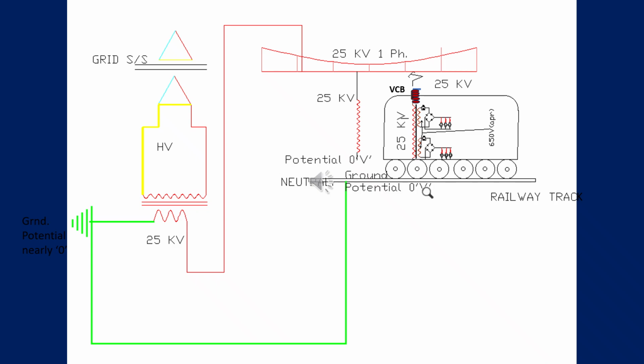So this is what we are receiving in the traction substation, and what a beautiful thing we have done there. One phase, the yellow phase, we have earth connected to ground. So many people are confused: sir, phase to earth, it will be a short circuit. No, it will not be a short circuit. What is a short circuit? A short circuit is to complete an electrical circuit without any load, without any impedance. But here you see the secondary of the 25 kV, one end is connected to the ground. So this yellow phase will attain zero potential, and the other end, the red phase, will be at around 25 kV.